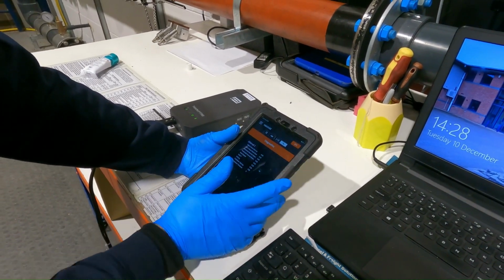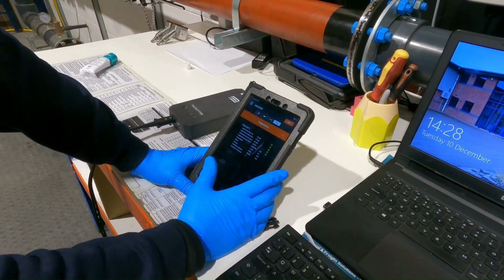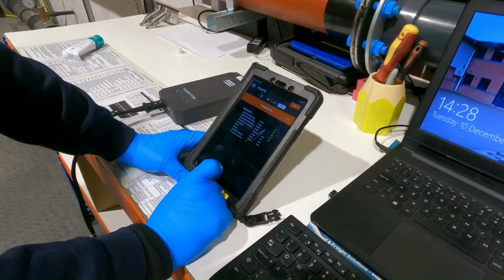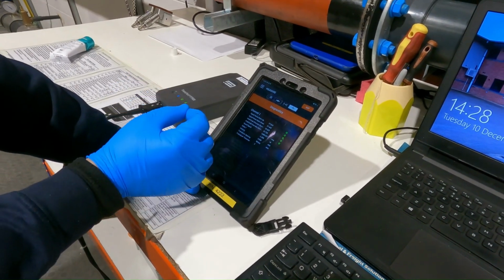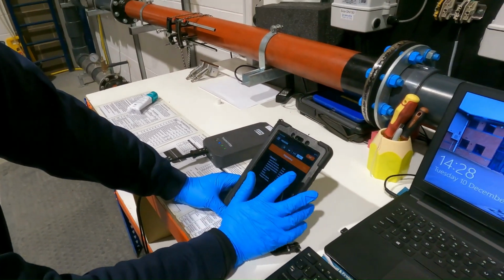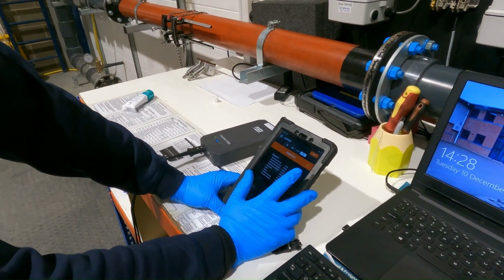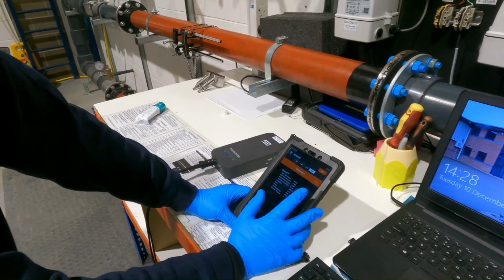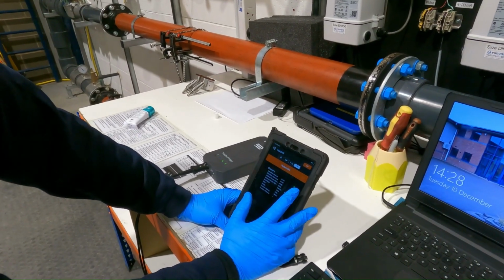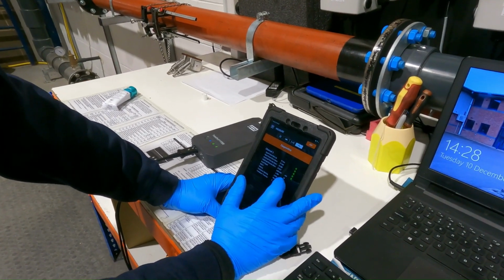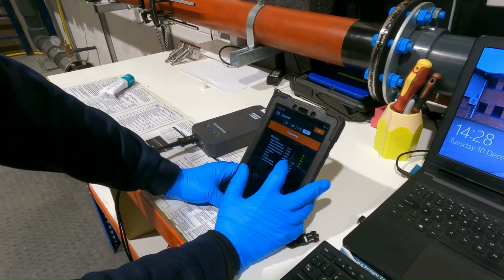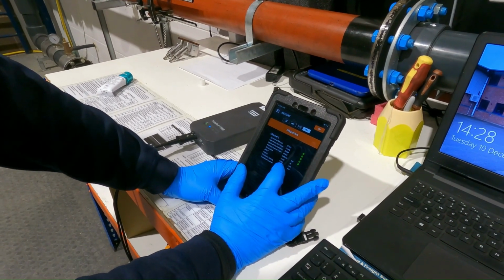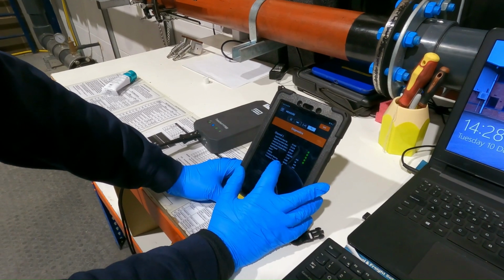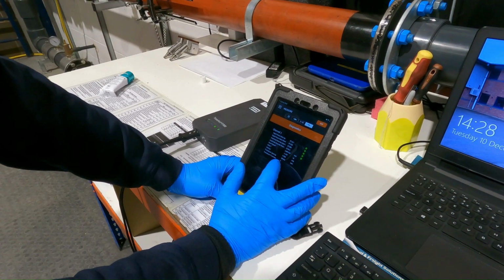And finally, the all-important diagnostic screen. You can see channel 2's there, but as we didn't select it earlier on, it's now greyed out. This will give you a signal to noise ratio up and down, your amplitude figures up and down, sound speed, the delta time, velocity, and just to remind you of your transducer spacing and traverses.